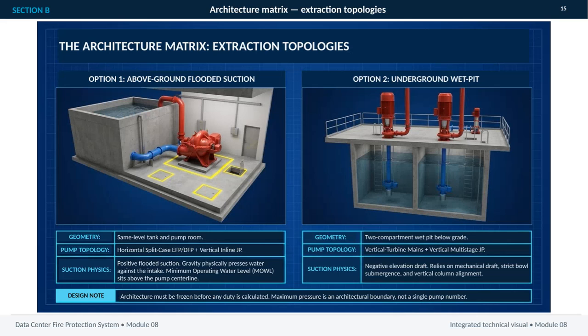This slide compares two extraction architectures, and the key distinction is how each arrangement creates suction at the pump. Option 1 is above-ground flooded suction. The tank and pump rooms sit at the same level, using horizontal split-case EFP and DFP pumps, along with a vertical inline jockey pump. Because the minimum operating water level remains above the pump centerline, gravity provides positive flooded suction. In practical terms, water is physically pressing toward the intake, which supports a straightforward and stable suction condition.